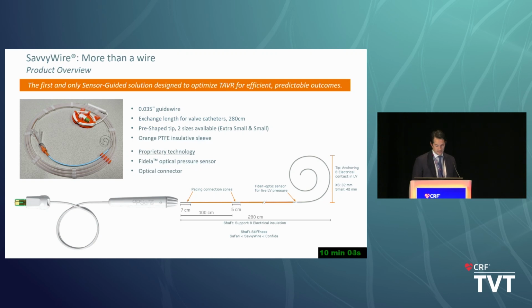It's a very nice color, orange. It's insulated with a PTFE sleeve, which allows for great conduction for the pacing. At the tip, on the LV side, there's a sensor, which allows you to have the LV pressure. And this is the pigtail tip, where you can pace with the entire tip of the wire. When you do the case, you can connect your alligator clip either at the distal tip, or there's a pacing zone, when the device is in, where you can clip more proximal in front of you. So that's the description of the device.